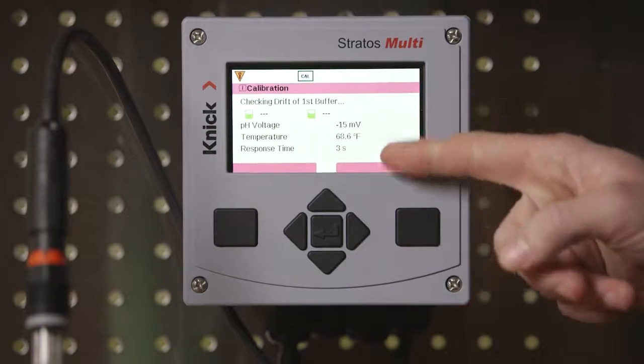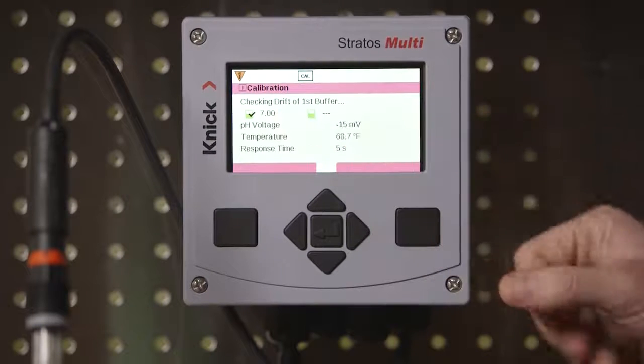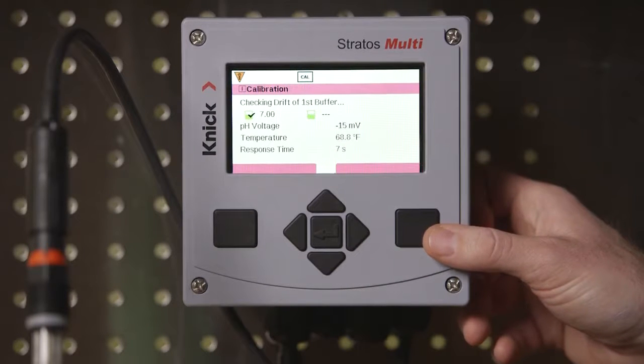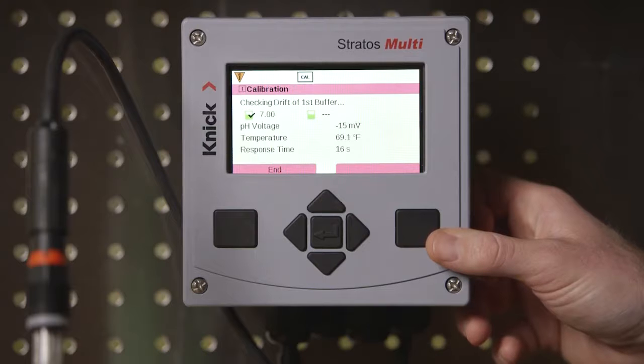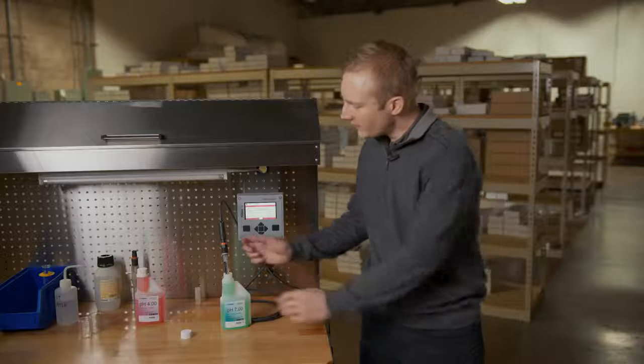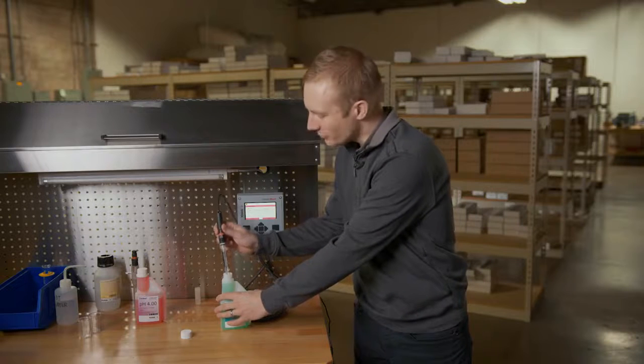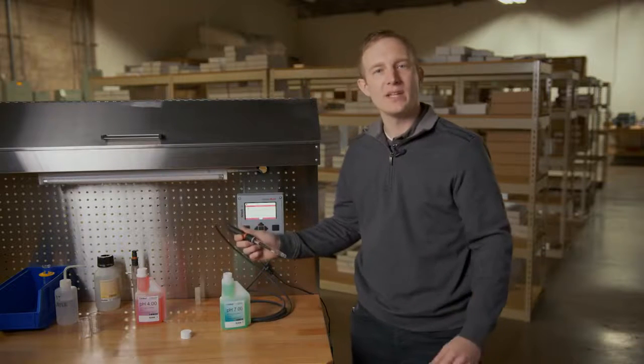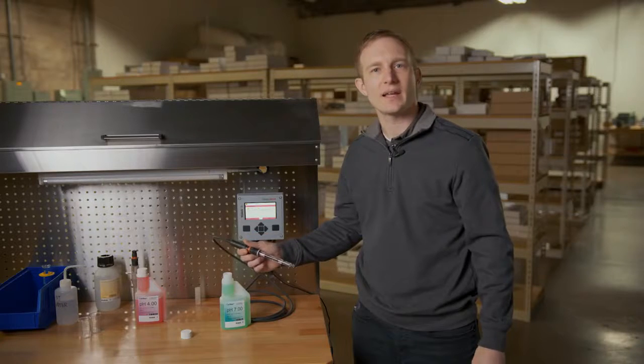After pressing Next, the transmitter will begin to check the drift in the first buffer solution. You can see that the buffer value is automatically recognized. The raw pH voltage value is displayed along with the measured temperature and response time of the electrode in the buffer. Once finished in the first buffer solution, the transmitter will prompt you to again rinse the sensor and immerse it in the second buffer.